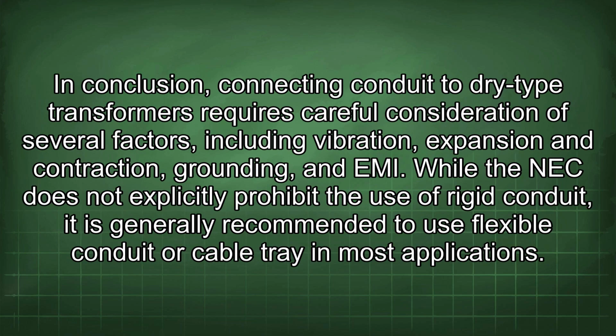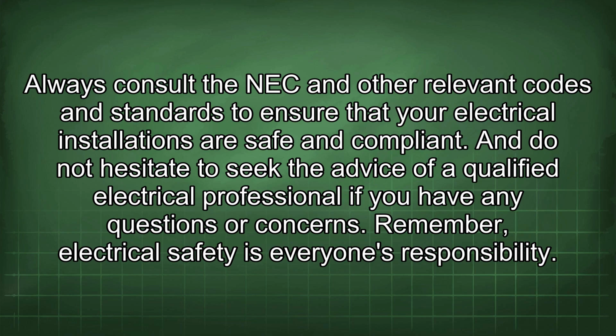In conclusion, connecting conduit to dry-type transformers requires careful consideration of several factors, including vibration, expansion and contraction, grounding, and EMI. While the NEC does not explicitly prohibit the use of rigid conduit, it is generally recommended to use flexible conduit or cable tray in most applications. Always consult the NEC and other relevant codes and standards to ensure that your electrical installations are safe and compliant. And do not hesitate to seek the advice of a qualified electrical professional if you have any questions or concerns.